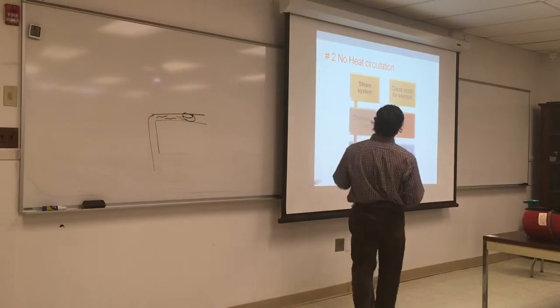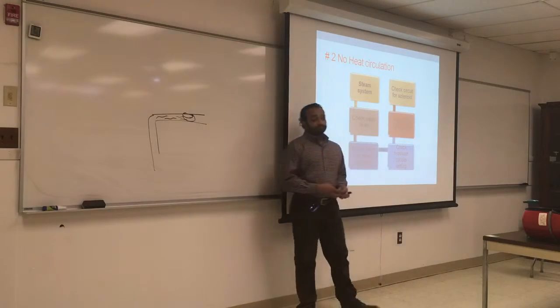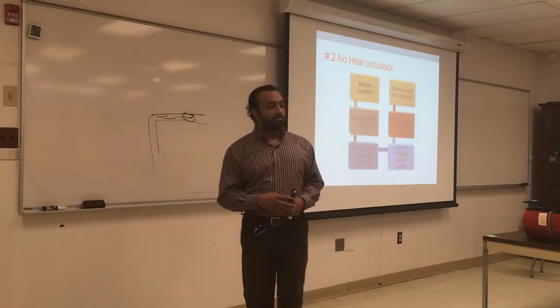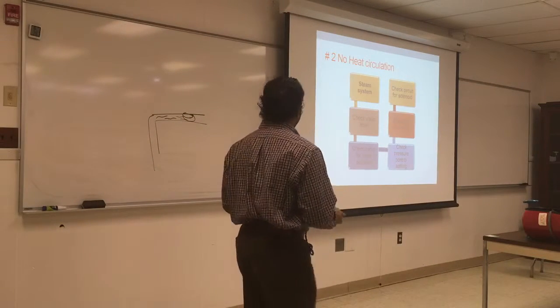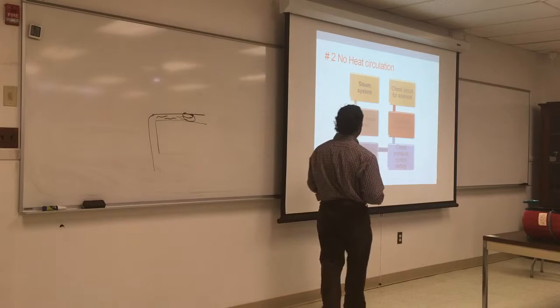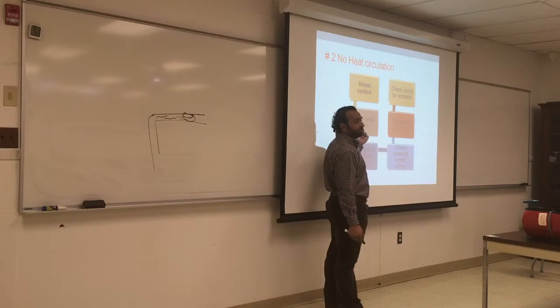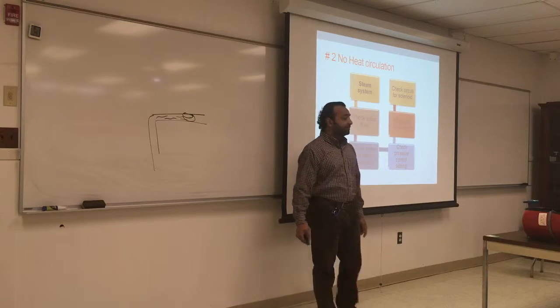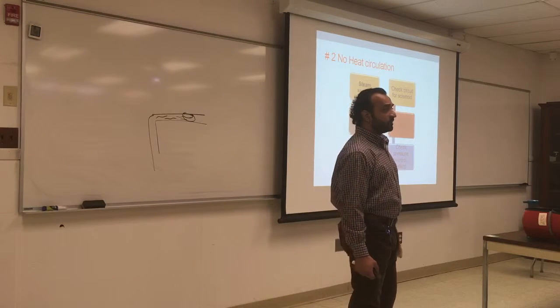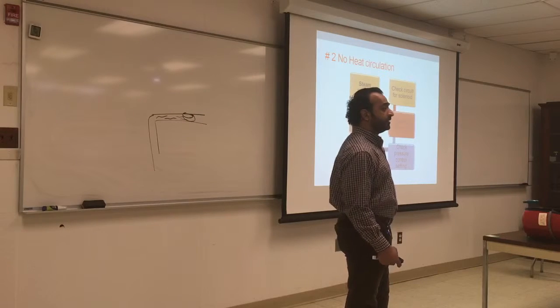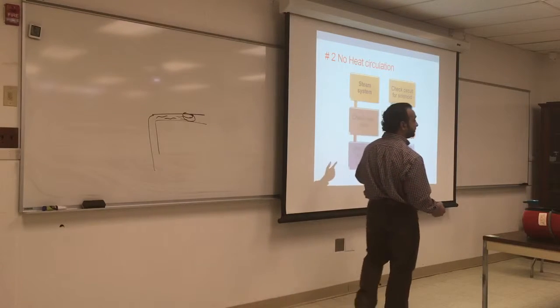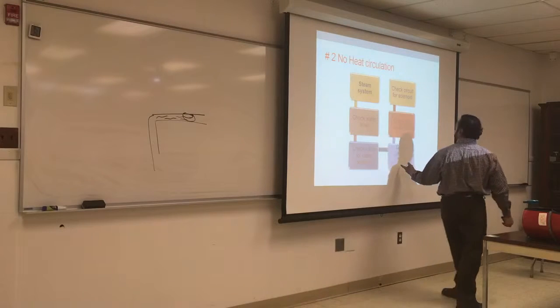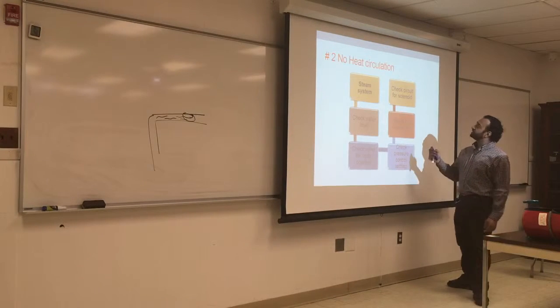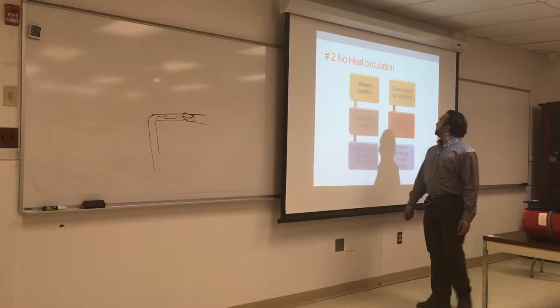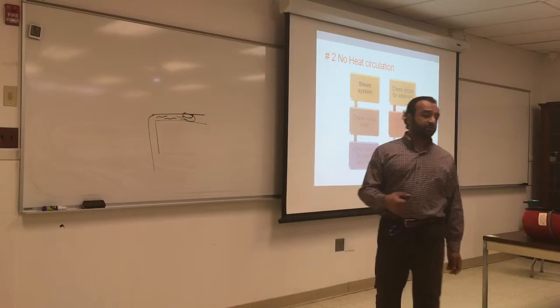No heat circulation again, this time for a steam system. Steam does not require a pump. The steam goes by itself. Check the water level. If you don't have enough water, you're not going to make enough steam to circulate. Check that the valve is in the open position. If you have a valve on the steam line and the steam is not going through, it's not going to move. Check the pressure control setting, main vents, and circuit for the solenoid if you have a solenoid.